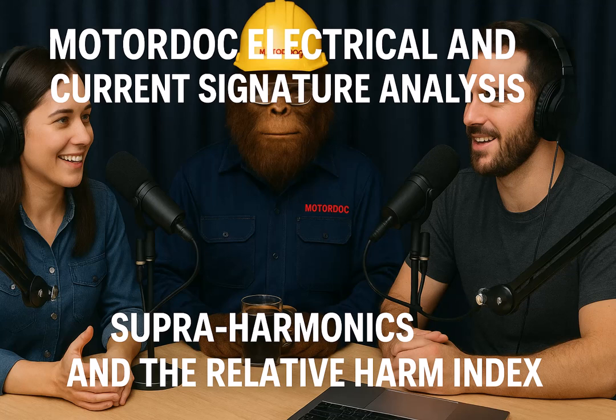And decibels, dB. Why use decibels for this analysis? Decibels are great because they give us values that are load-independent and repeatable. Load-independent, okay. How? Instead of just raw signal size, which can change with load, dB gives a relative measure. The formula is 20 times the log base 10 of the defect current divided by the line frequency current, IDIF. Got it.